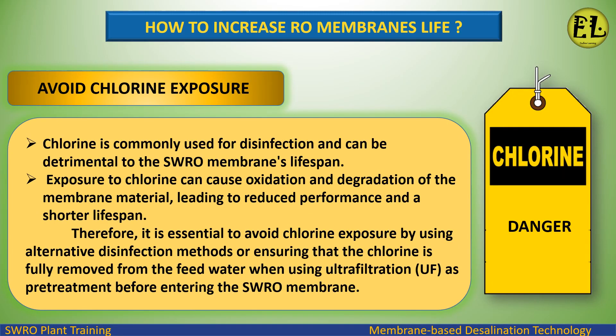Chlorine is commonly used for disinfection but can be detrimental to the SWRO membrane's lifespan. Exposure to chlorine can cause oxidation and degradation of the membrane material, leading to reduced performance and a shorter lifespan. Therefore, it is essential to avoid chlorine exposure by using alternative disinfection methods or ensuring that chlorine is fully removed from the feed water, particularly when using ultrafiltration (UF) as pretreatment before the membrane.